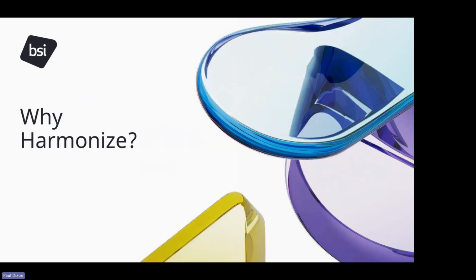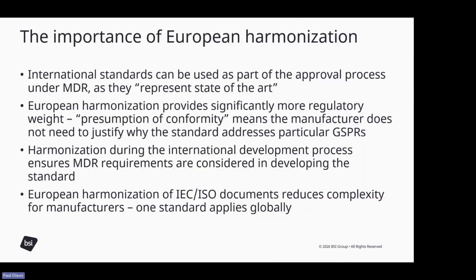The first section, why harmonize? The importance of European harmonization, essentially international standards always have been and can be used as part of an approval process for medical equipment under the medical device regulation, as international standards represent state of the art. But European harmonization provides significantly more regulatory weight. There's a presumption of conformity, which means that a manufacturer doesn't need to justify why a particular standard addresses particular general safety and performance requirements of the medical device regulation.